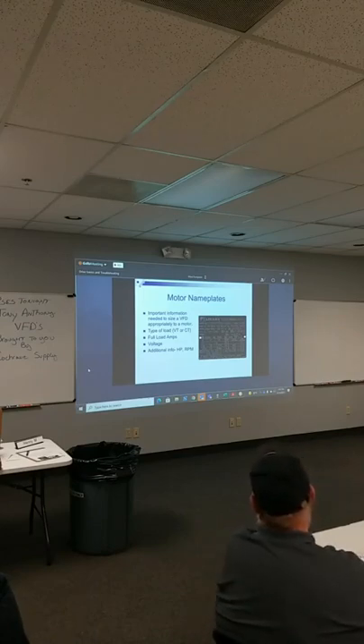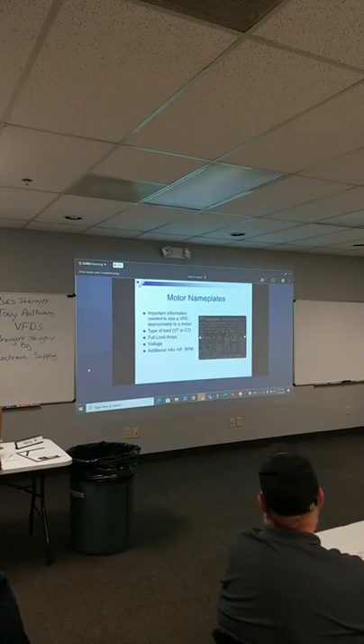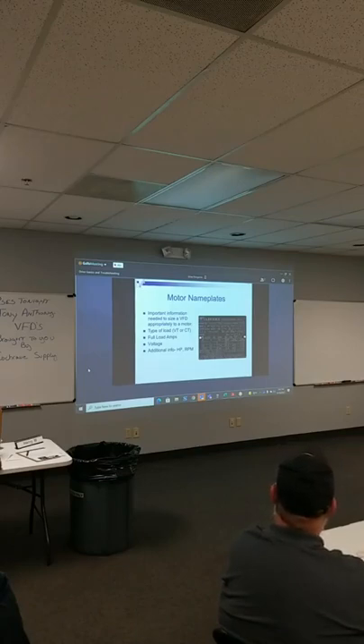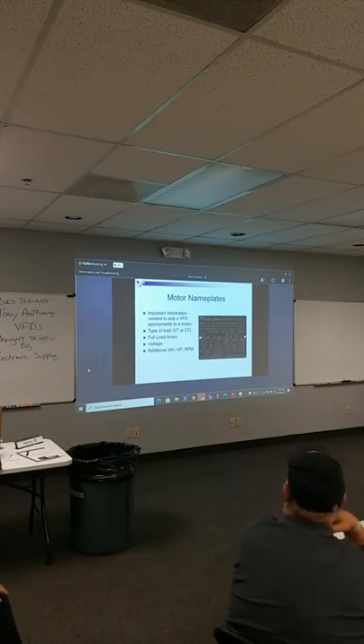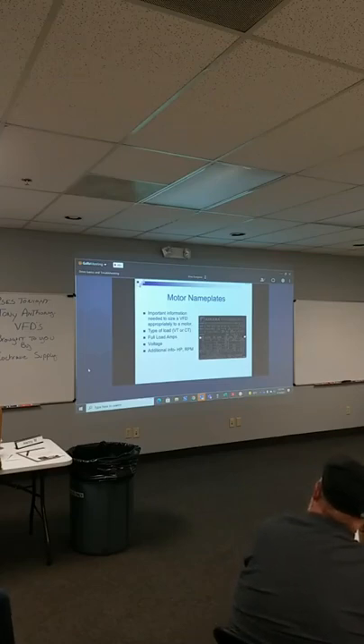Because the full load amps, depending on the type of motor, can change. A 10 horsepower, severe duty, 900 RPM motor is going to draw a lot more current than an 1800 RPM NEMA B motor. Every drive is sized based off of a NEMA B 1800 RPM motor. You start lowering those speeds and getting more severe duty, higher service factor motors, and the full load amps will go up. Sometimes if you've got a 10 horse motor, you may need to put a 15 horse drive on it, because it's a 600 RPM special duty motor that draws more current. The current is so important to know in the application.